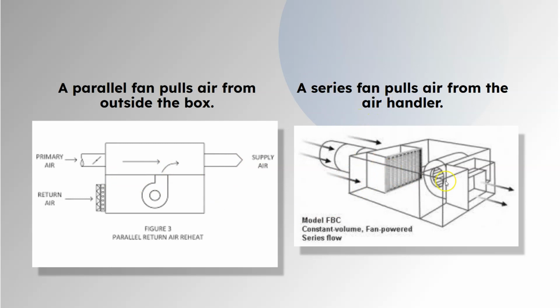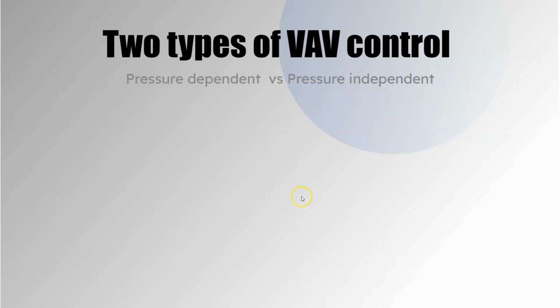A series is different. Now, a series will always pull air from the ductwork, from the air handler. So it's like a booster fan. So a series is going to run in cold or hot conditions. It's always going to be pulling air from the air handler. And there's two types of VAV control. There's pressure dependent versus pressure independent.